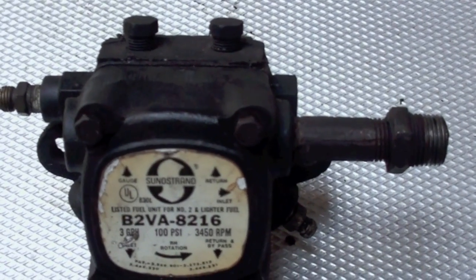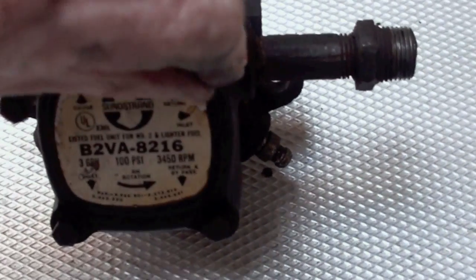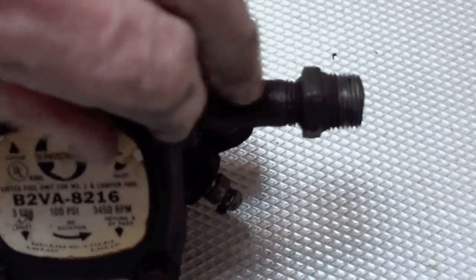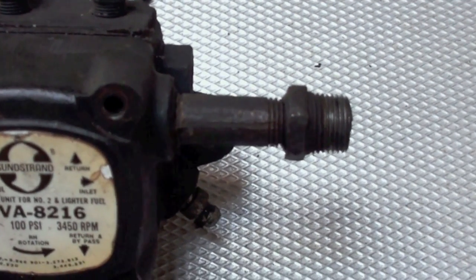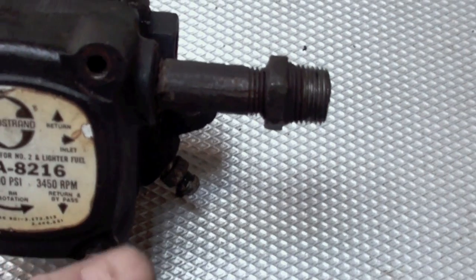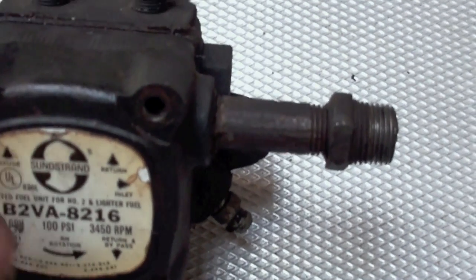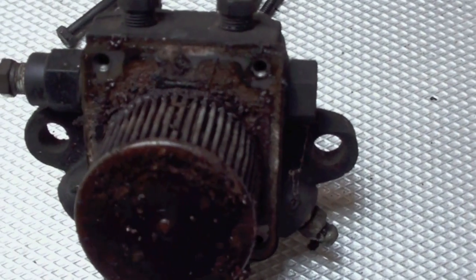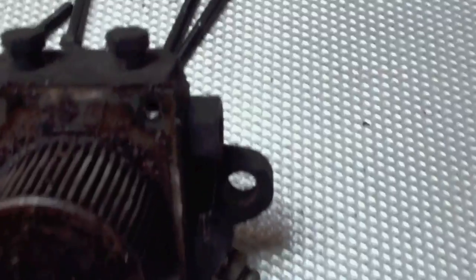Here we have a little Sundstrand mini pump that locked up and we're going to take a look inside and see what we find. These mini pumps run at 3450 RPM. The older pumps ran at 1750 and they were heavier made — they would survive things these pumps won't. To get this cover off you can see inside — this thing has had water in it, assorted garbage, it's pretty ugly.